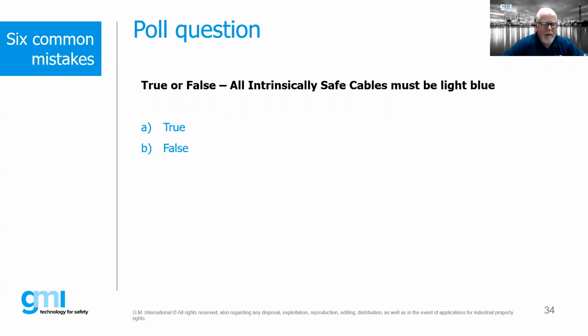What almost all of the standards say in some way, shape, or form - and this is somewhat a generality because every country could be slightly different - generally speaking, if we're going to use color coding to indicate intrinsic safety, that color coding shall be light blue. However, it does say that we can mark our cables and we don't have to use light blue cable, but we do have to indicate that cable or wiring is actually intrinsically safe.